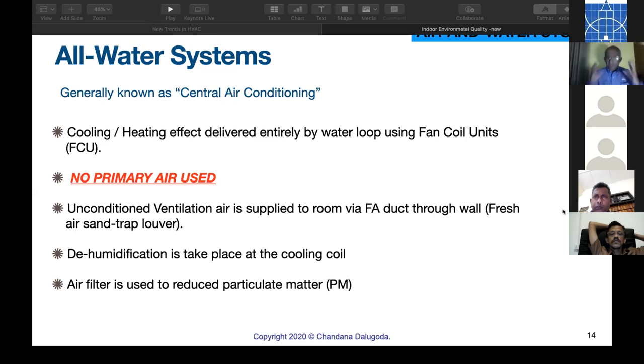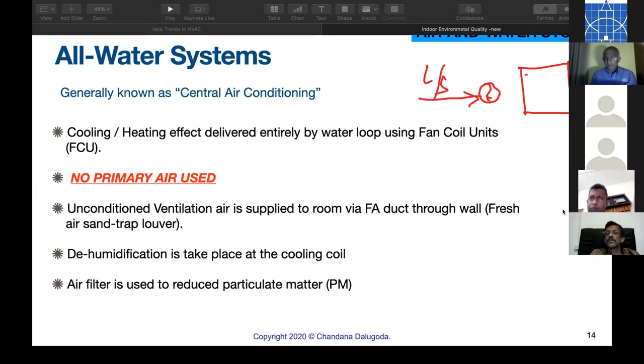The definition of a central air conditioning system is a refrigeration machine located centrally, and it is basically an all water system. That means primary energy transfer is by water. No need to explain. If you take a pipe cross-sectional area, this will have a certain water flow rate, liters per second. The same amount of energy is carried by a duct on the other side. Let's say this is 100 millimeter diameter. This might be 600 by 600.